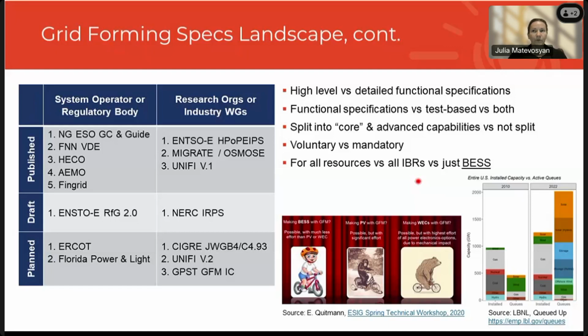And also grid forming capability is more straightforward to implement in storage, because grid forming capability requires some energy buffer, and that already exists in storage. In solar, there is another challenge: you need to have energy margin behind the inverter to provide grid forming capability.